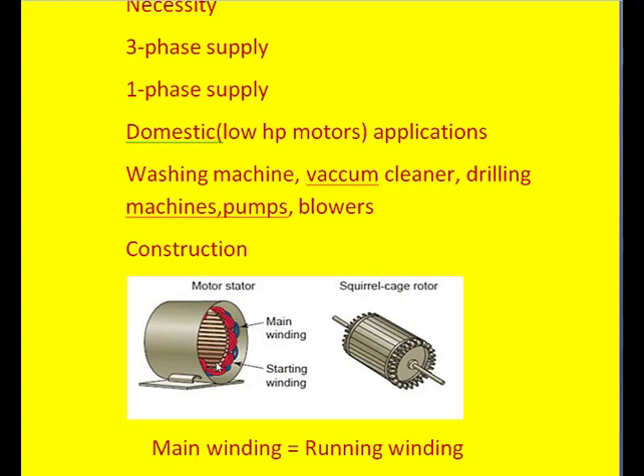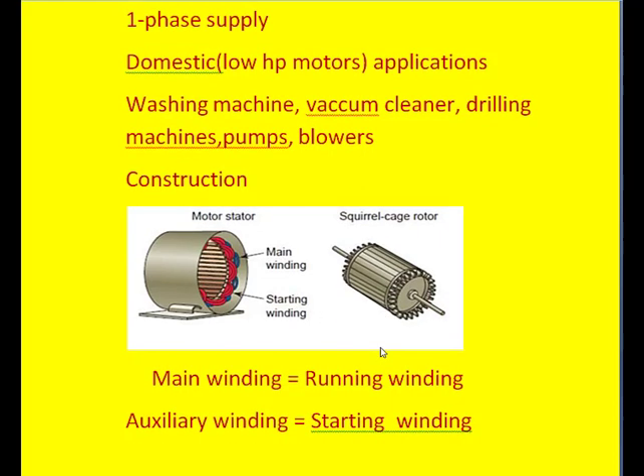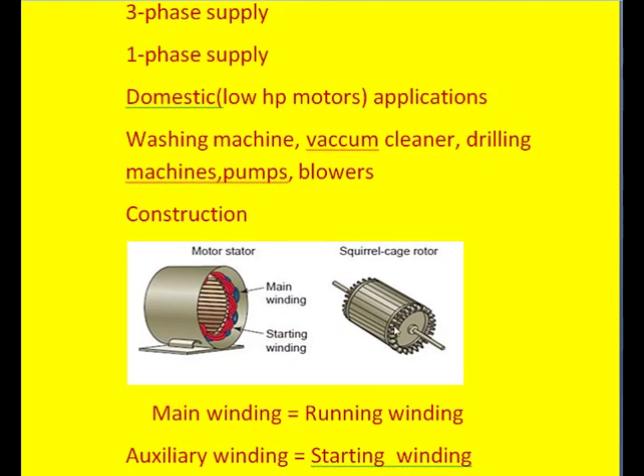The main winding is a thick wire, large number of turns, contributes low resistance, high inductance. Coming to the starting winding, it is a thin wire with less number of turns, contributes high resistance, low inductance. And coming to the rotor, it is a squirrel cage rotor.